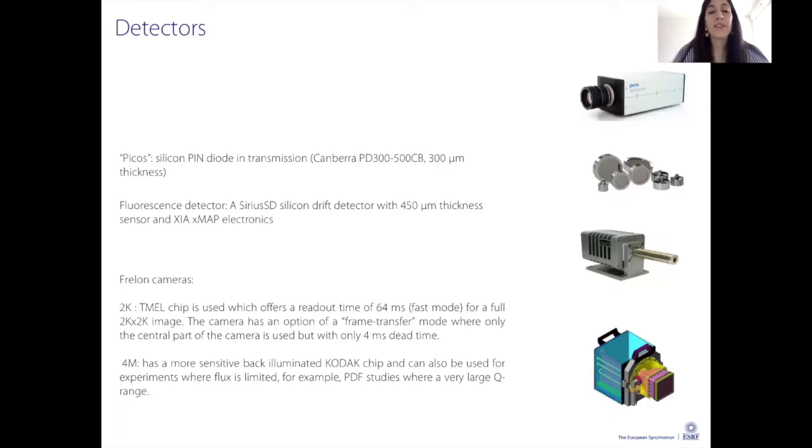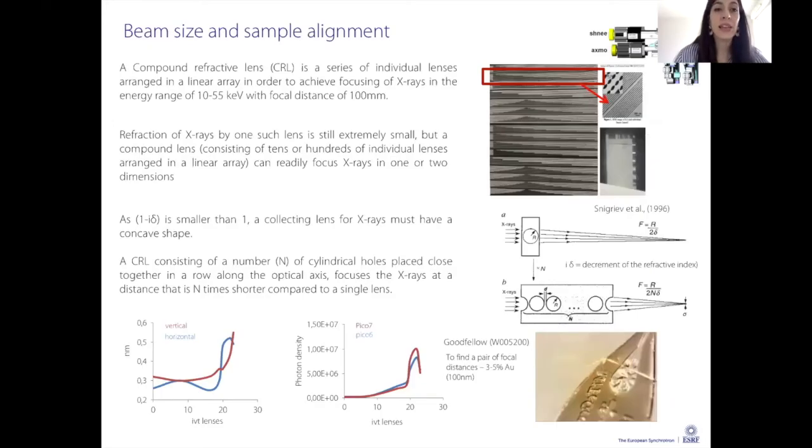You can have several detectors. In the picture before you could see a Dectris detector was mounted. We can also provide a fluorescence detector that we can use either to collect data at the same time we're collecting diffraction data, or just for alignment purposes. For the FReLoN cameras, you will see that in the next months the FReLoN camera will change - we won't have a FReLoN camera anymore but will have an Eiger detector.